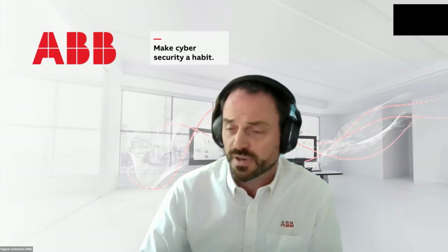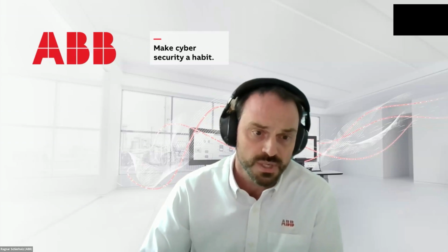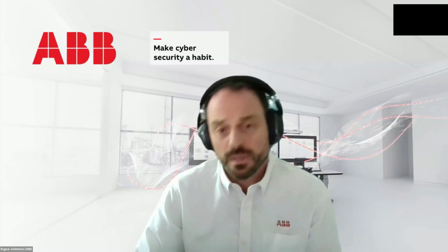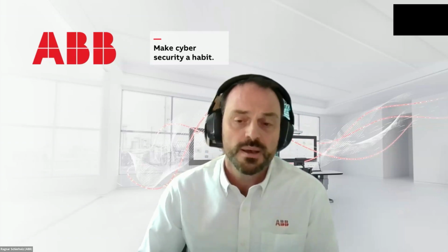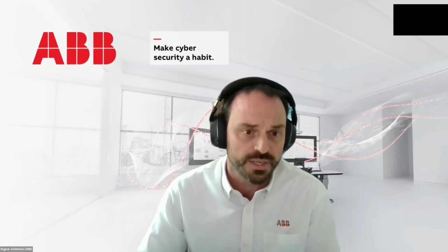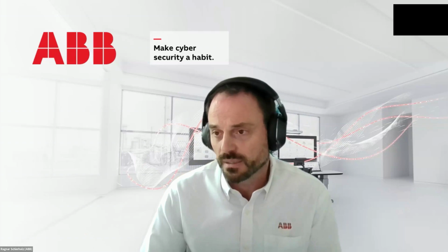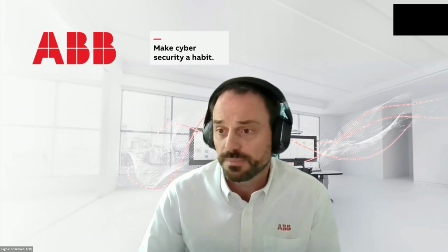And as long as the firewall rules allow the Nozomi data collectors, the sensors, to communicate with the console, which obviously is a requirement, that can be very much in line with the Purdue model and 62443 compliant zoning, because it's only outbound connectivity. I think that is a clear yes, they can go hand in hand.